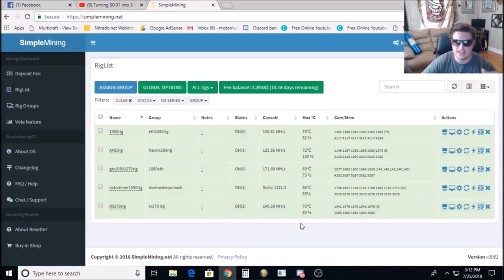And now the 570s are at 58, 70, 67, 58, 70. I'm going to take y'all upstairs in a second, but I just wanted to reiterate that it does not necessarily have to be air conditioned, as long as you have airflow stripping the air off the heat sinks. If you have passive airflow across those heat sinks, pulling that heat out of there, that's the biggest thing.